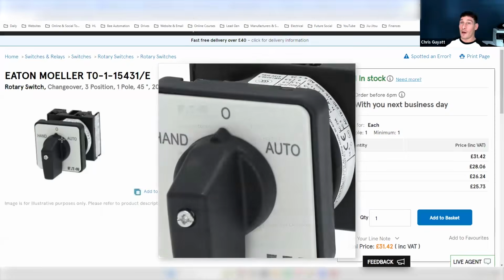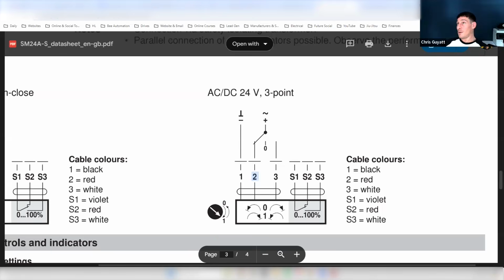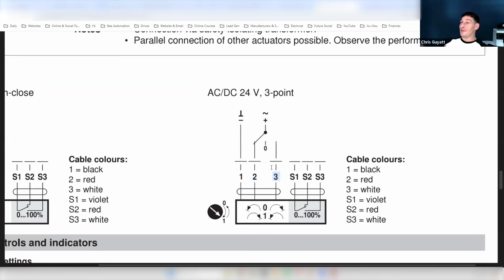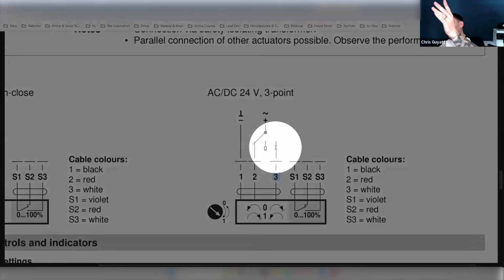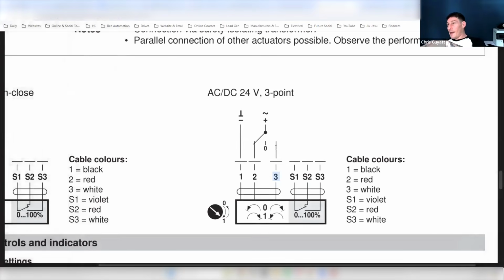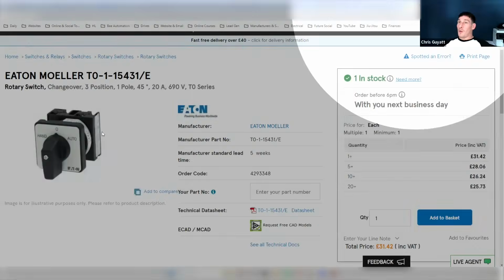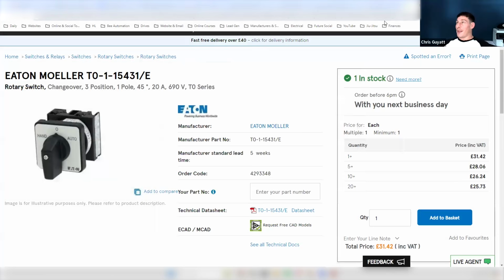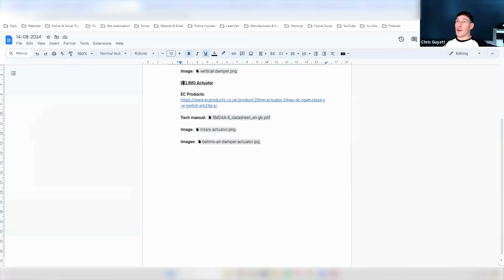Then if we switch that switch over to auto, which is 3, and apply that for 10 seconds, that will then close it. And if we bring it back the other way to 2, and power it for 5 seconds, that will open the vent to 50%.